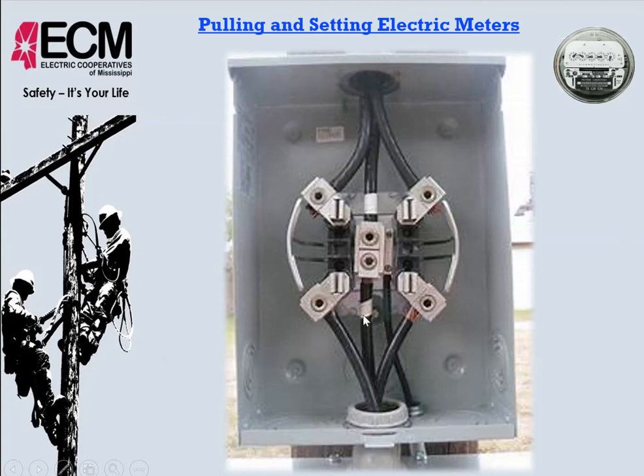And also you'll notice that the neutral is identified on the line and the load side. Talk about that more later on in the program. And then you'll see that their wire going to their grounding lug is a separate piece of wire. It's insulated as well. And actually they have it in conduit just to give it some extra protection. Now, it does not have to be insulated or coated, but it definitely is beneficial to us if it is, and then it being in conduit, conduit definitely helps to protect it as well.